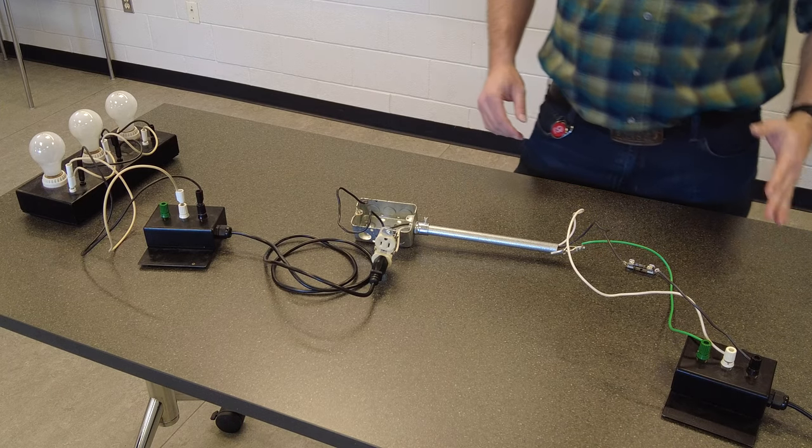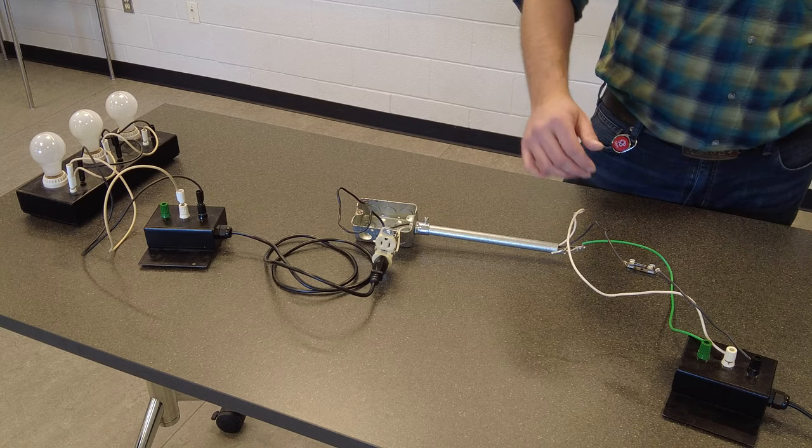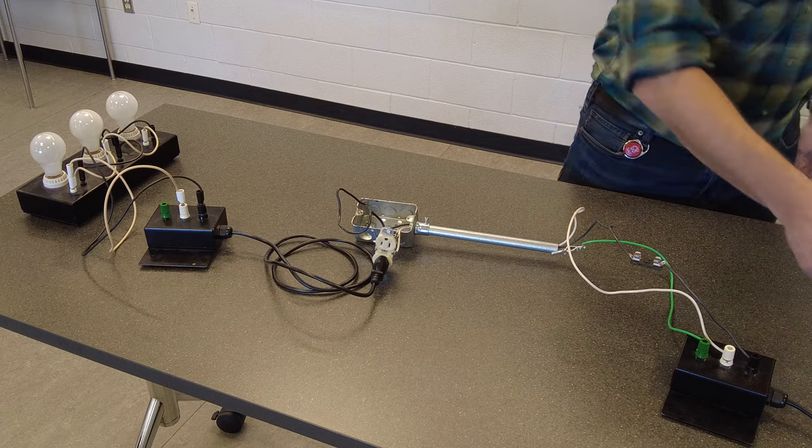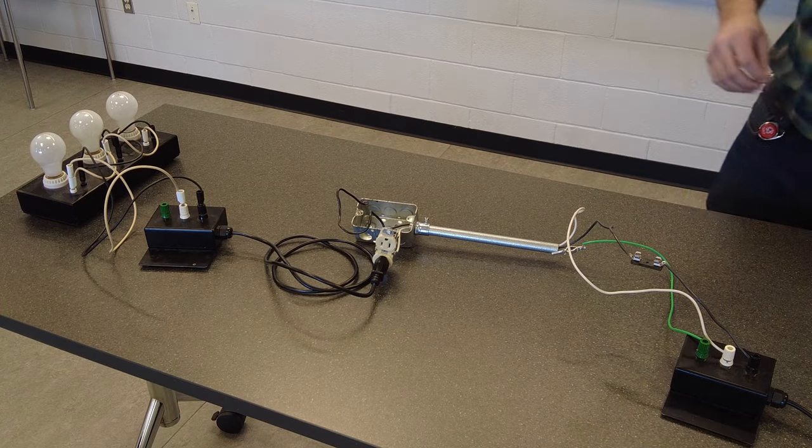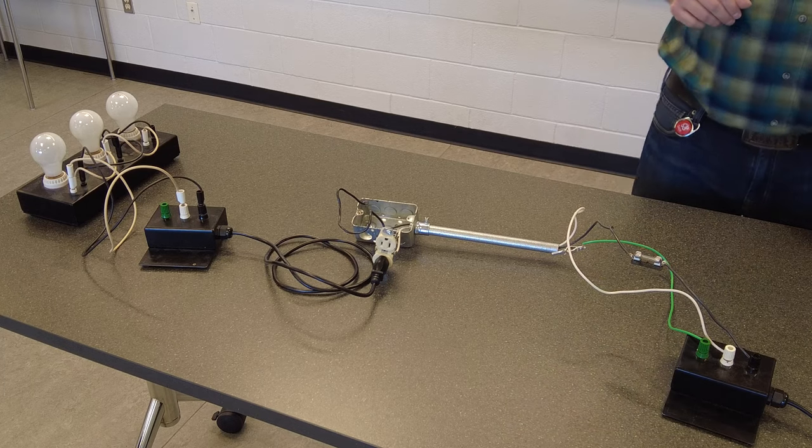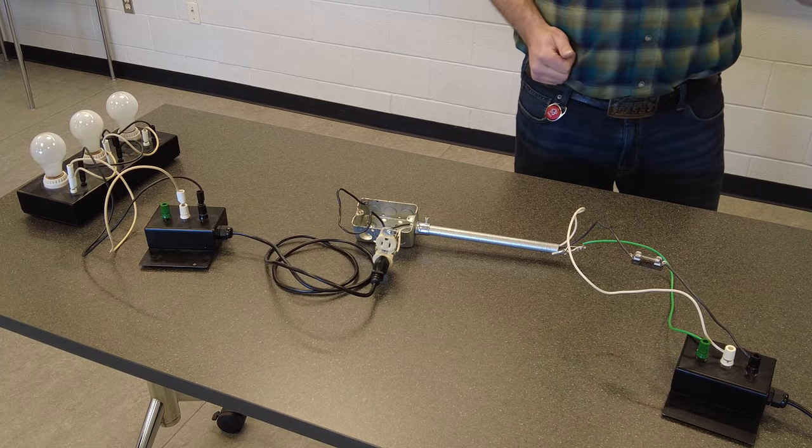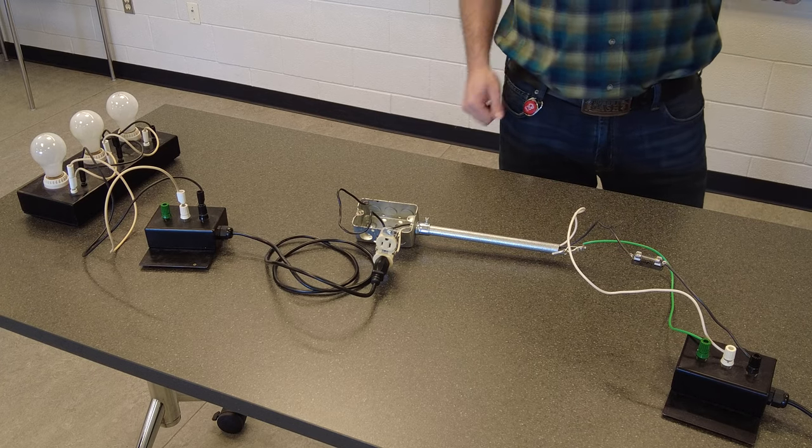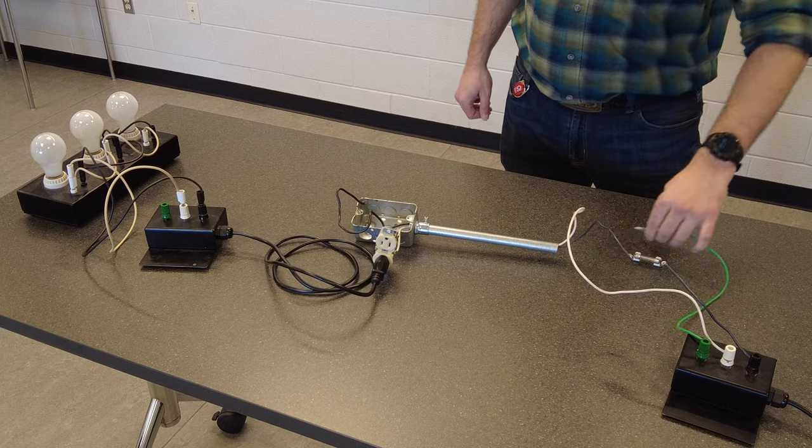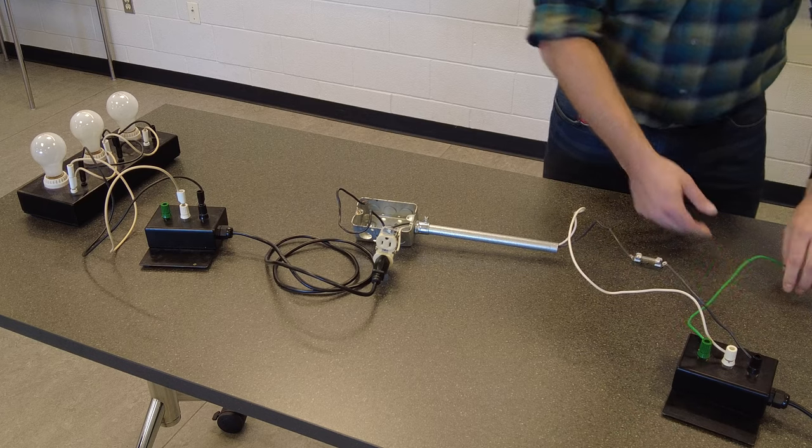So in the next example, what we're going to do - I've de-energized everything. Always make sure everything is de-energized whenever you're removing live components, but we're going to replace this 5 amp fuse with another 5 amp fuse. And we're going to see exactly what happens again. So we're going to re-energize this, but I'm going to make one critical difference in this system. I'm going to disconnect this bonding conductor, that one little green conductor that seems like it doesn't do much.